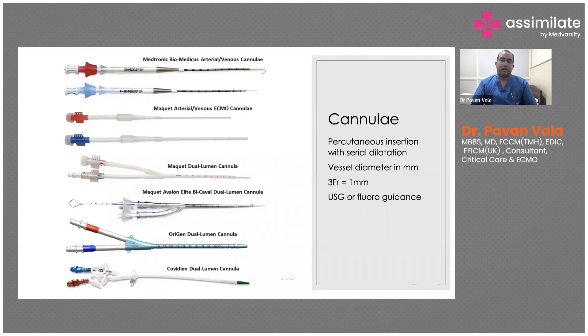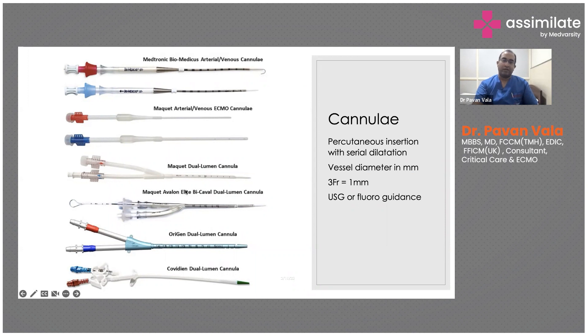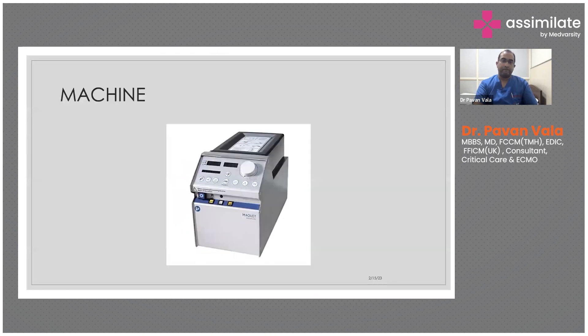These are some of the cannulas available on the market. You have Maquet cannulas, or you can use what's called an Avalon cannula. In VV-ECMO you can either have two cannulas in two different veins — femoro-jugular — or the Avalon, which is a single cannula with two different outlets placed in the right jugular, used for both drainage and return.